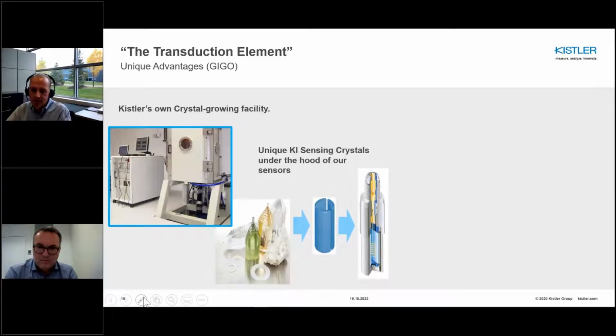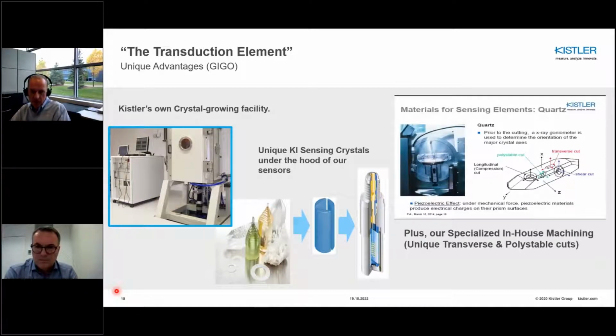Let's get the laser pointer. The green or the amber or the white. So we're using more than one crystal in our sensors. That's how we're actually tailoring the performance of the sensor, either the sensitivity or thermal performance, to our customers' needs. On the far right of this illustration, we provide a glimpse of our in-house ability to precisely machine each sensor's crystal, thus ensuring the overall sensor's performance to our customers' needs.